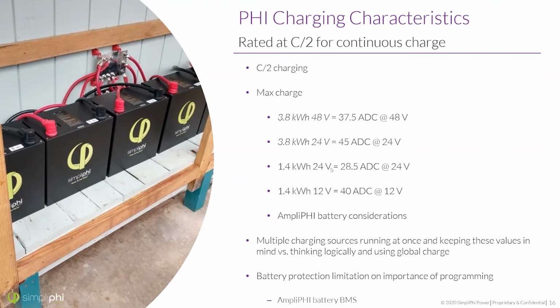The 1.4 kilowatt hour model is about 28.5 amps DC per 24 volt, and 40 amps DC per 12 volt battery. The AmpliPHI is the same as the 48 volt, 37.5. However, just note the AmpliPHI does all of the settings through the BMS. It can auto-populate settings. So if it's plugged into an inverter that it communicates with, it will automatically tell it what its max charge rate is.